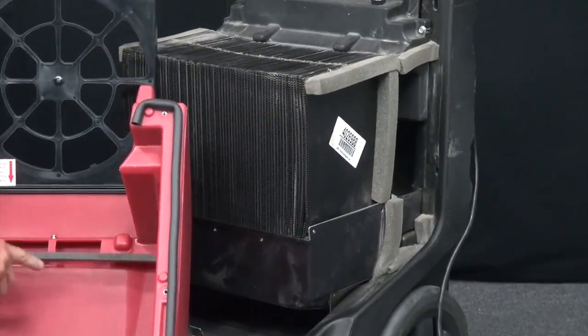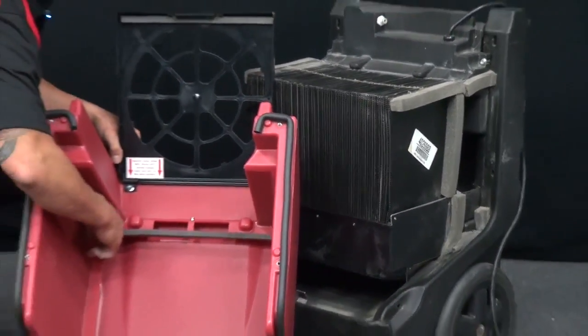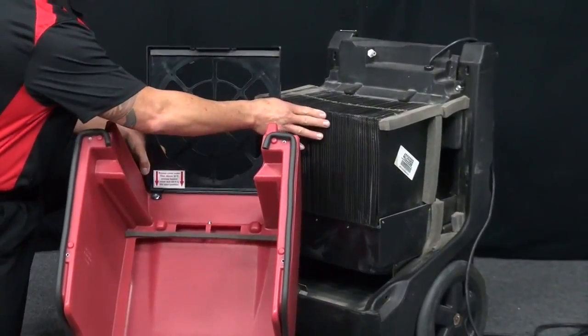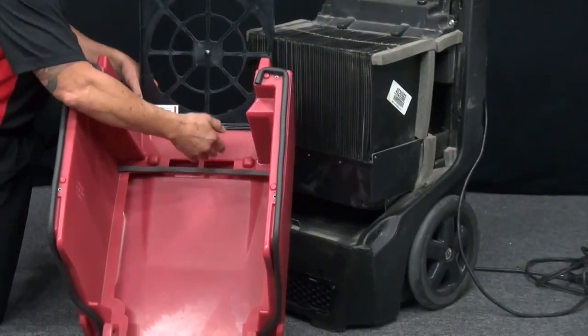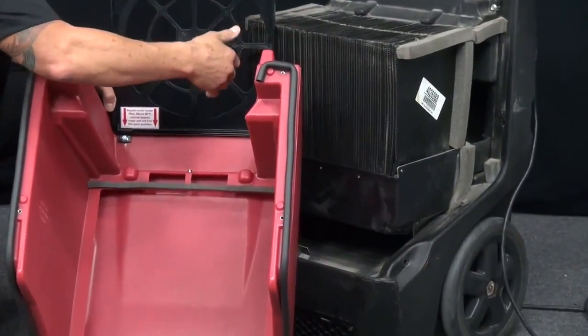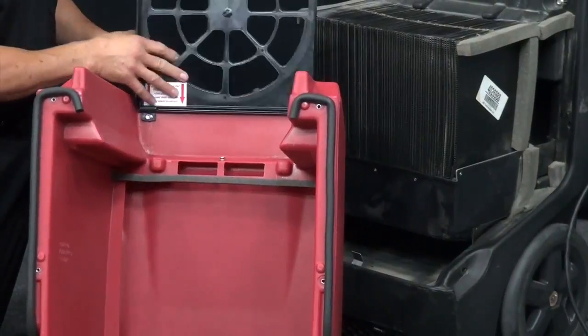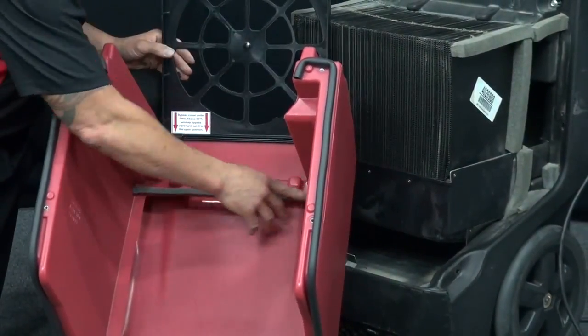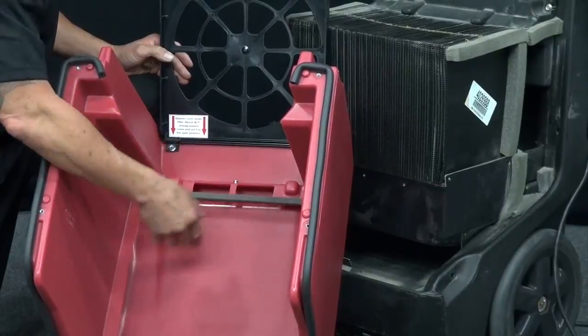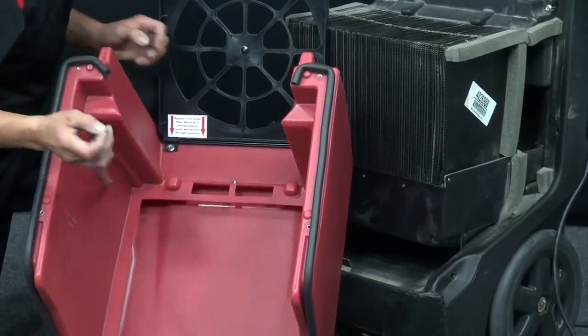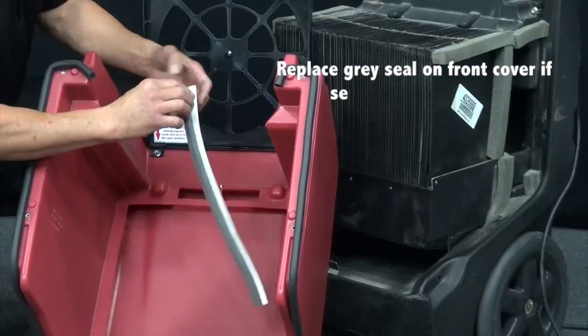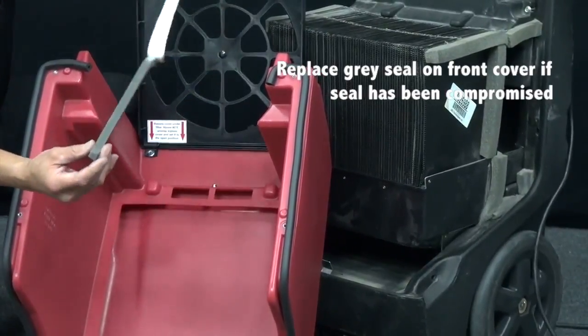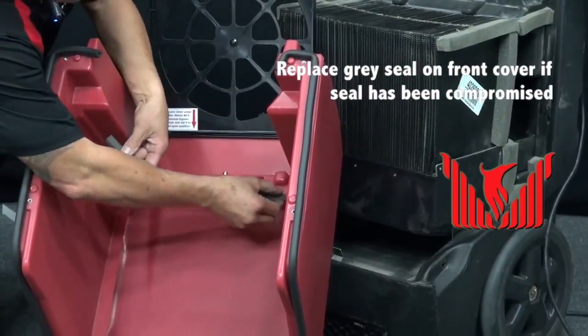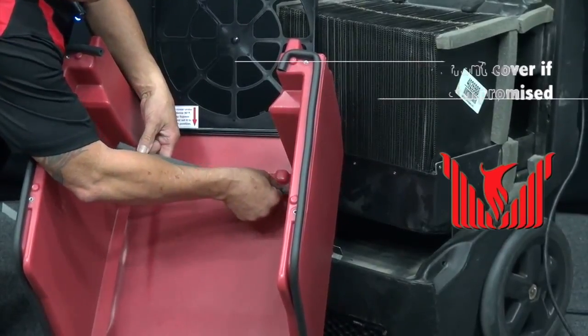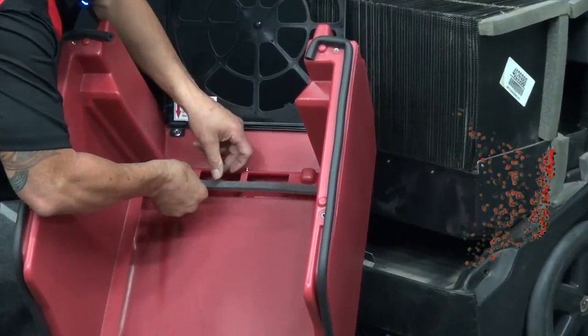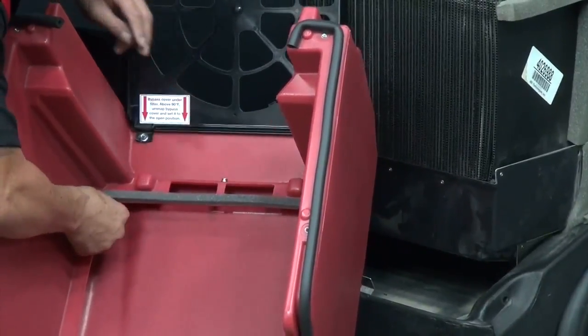Next, it may be necessary to replace this seal, which seals the front cover to the front of the heat exchanger. If this seal was not here, it can create a huge leak, causing the unit to go into defrost prematurely. If this seal is not compromised, it is okay not to replace it. If you do have to replace it, just simply take the new seal, start at the end, and fasten it to the front cover.